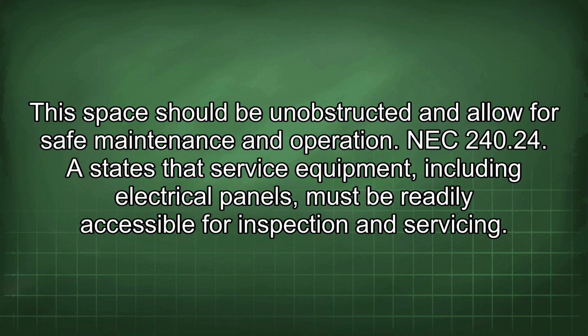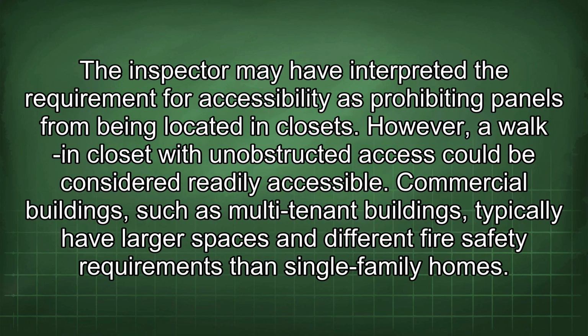NEC 240.24 states that service equipment, including electrical panels, must be readily accessible for inspection and servicing. The inspector may have interpreted the requirement for accessibility as prohibiting panels from being located in closets. However, a walk-in closet with unobstructed access could be considered readily accessible.